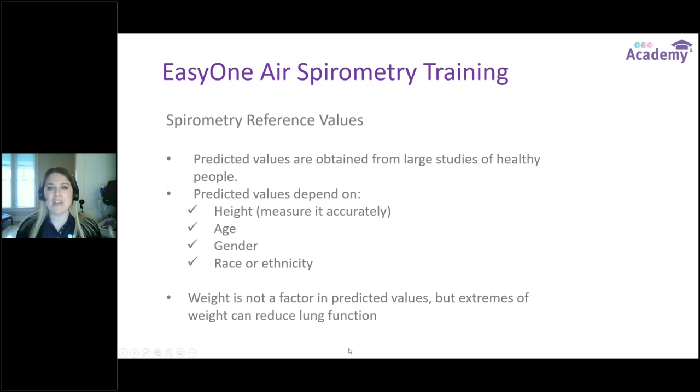Spirometry reference values — where do we get our normals from? These predicted values are obtained from large studies of healthy people. Predicted values depend on the patient's height, which we always want to measure accurately, their age, biological gender, and race or ethnicity. On the EasyOne Air spirometer there is an option to input weight. Weight is not a factor in predicted value sets, but extremes in weight can reduce lung function, and the device uses weight to calculate a BMI for the provider.